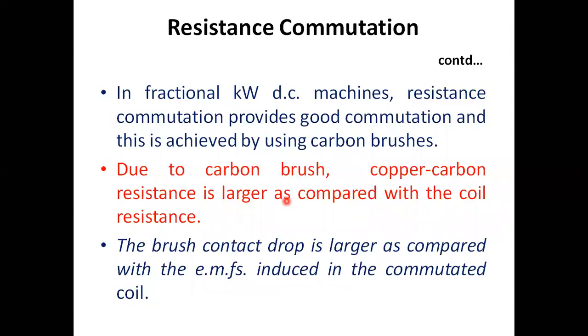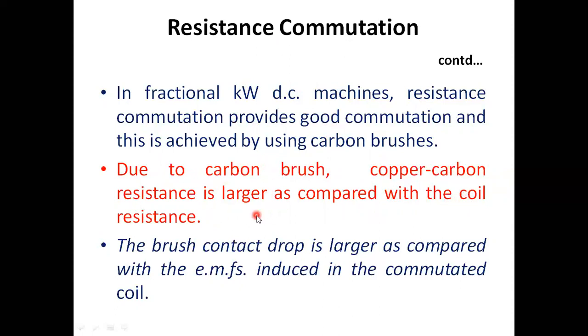In fractional kilowatt DC machines — that is, small machines — resistance commutation provides good commutation, and this is achieved by using carbon brushes. The copper-carbon contact resistance is larger compared to the coil resistance. That is why this method provides good commutation, provided the machine is a fractional kilowatt motor, where the brush contact drop is larger compared to the EMF induced in the commutated coil.